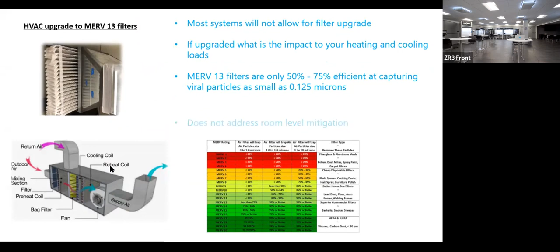To dive a little bit deeper with the MERV filter, again, it starts at MERV 1 and can go all the way up to MERV 20, which is a HEPA filter, but this slide shows you the effectiveness between the different types of MERV filters. So really, as you see here, MERV 13 filters still really aren't great. You're looking at between a 50 and 75% efficiency, which is not good enough. And again, if a MERV 13 filter is in the HVAC system, it's only effective when the HVAC is on. So really, a HEPA filter is critical because it does capture 99.97% of particles down to 0.1 micron.